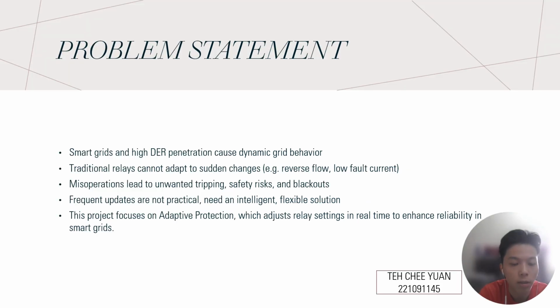So let's look at the core problem. In modern smart grids, especially those with high DER penetration, the grid behavior becomes much more dynamic. The direction and strength of power flow can change suddenly, like when a solar panel drops output or an EV starts charging. Traditional relays cannot adapt to these changes.